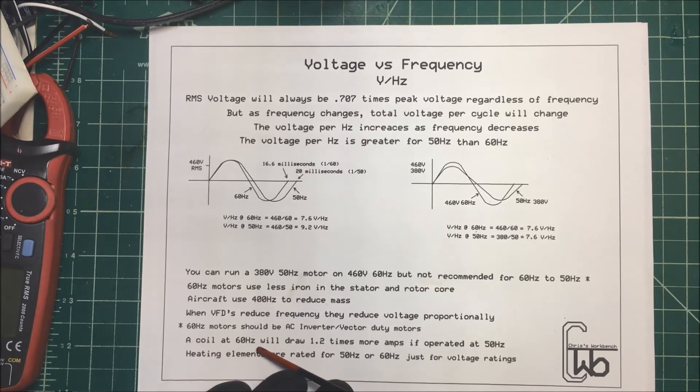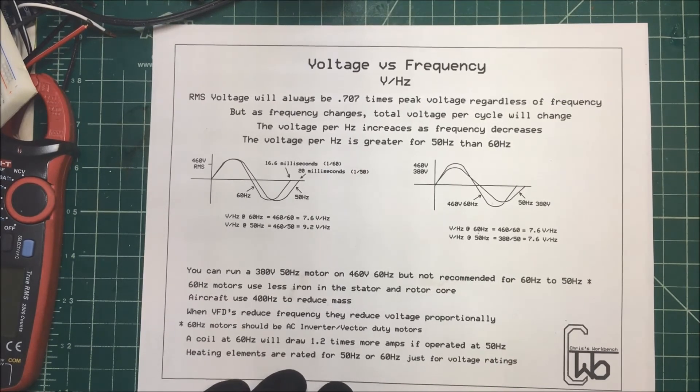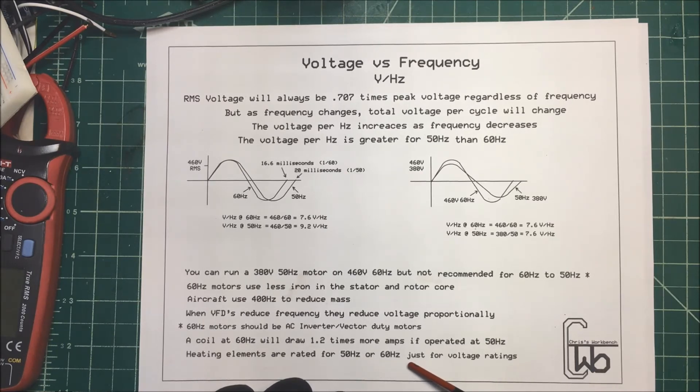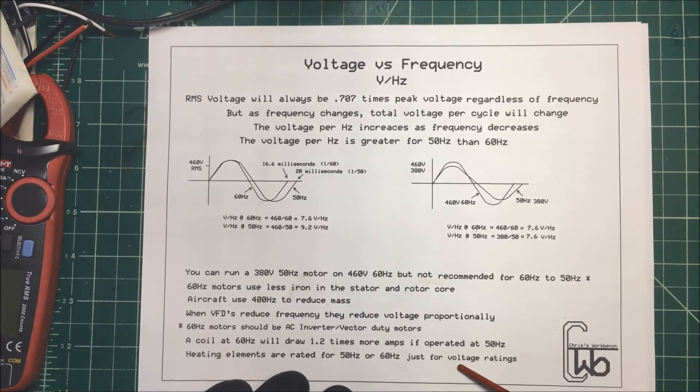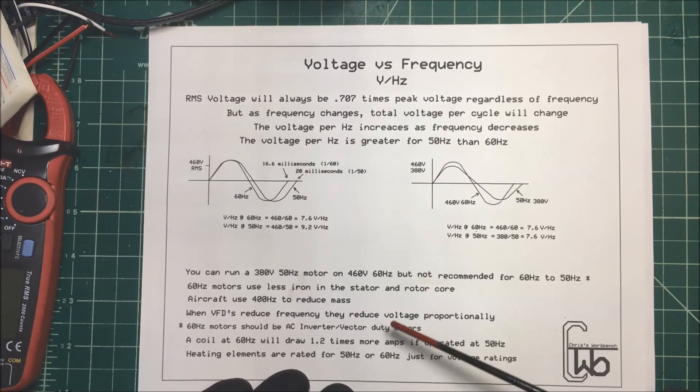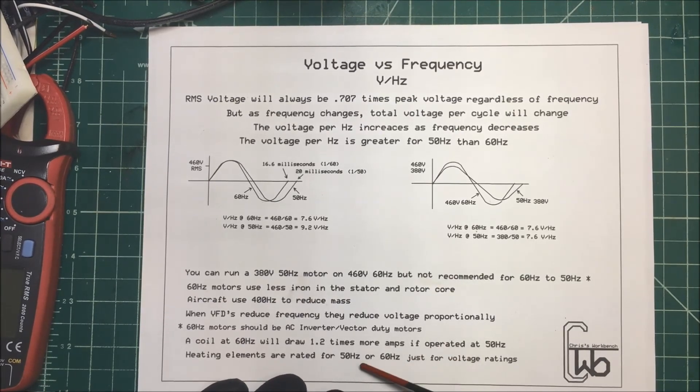So now if you take a coil at 60 hertz, it'll draw 1.2 times more amps if you operate it at 50 hertz. Now heating elements, they're rated at 50 hertz and 60 hertz, but that's just for voltage ratings. The RMS value is going to be the same, so the heating value is going to be the same, but a 50 hertz heater is going to come out at 230 volts and a 60 hertz one is going to come out at 240 volts. It's kind of a typical voltage for an element there.